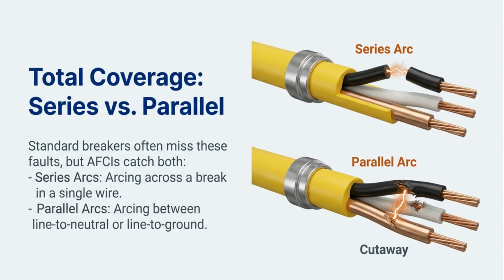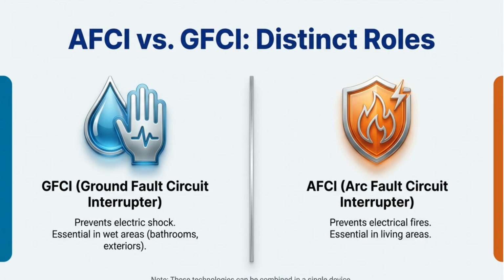AFCIs provide total coverage against both series and parallel arcs. Standard breakers often miss these faults, but AFCIs detect arcing across a break in a single wire and arcing between line to neutral or line to ground.